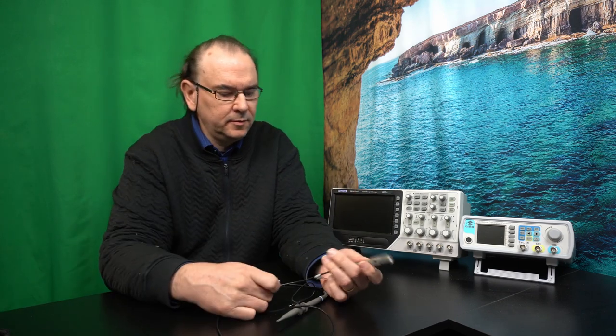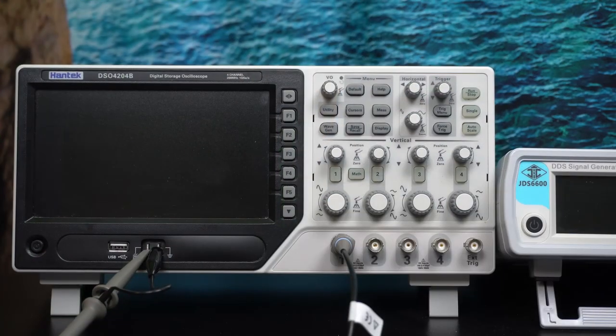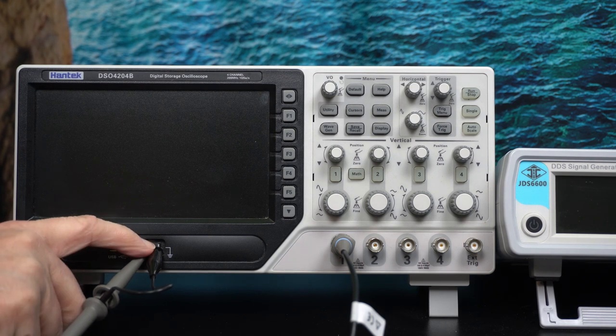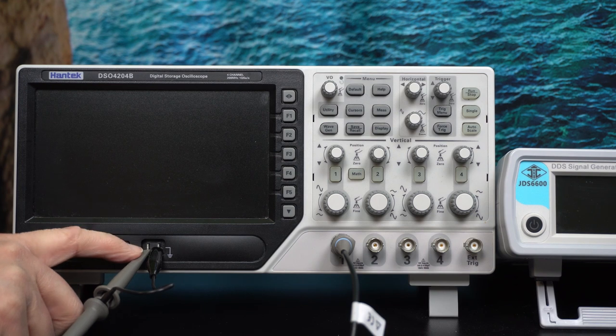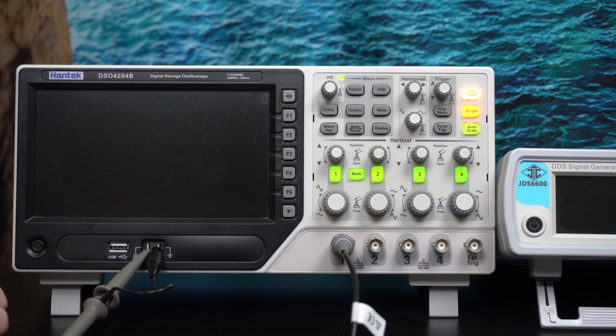Probe calibration. There is a calibration point on the probe — basically a screw where you adjust the calibration. And if you're a little bit of a trickster, you can change it to frustrate your friends. So let's start with the startup process and do the calibration. I've already connected the probe to input channel one, the ground goes into the ground reference point, and the probe tip gets connected to the plus side of the calibration signal.